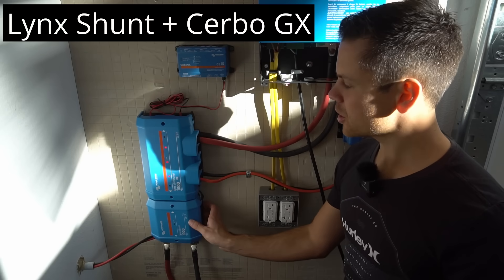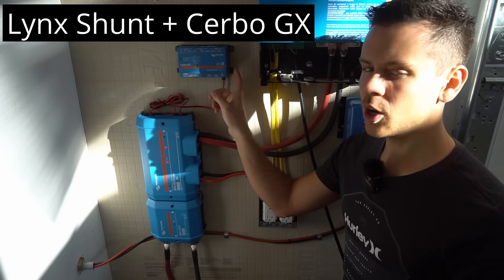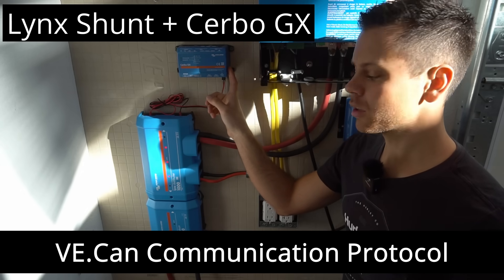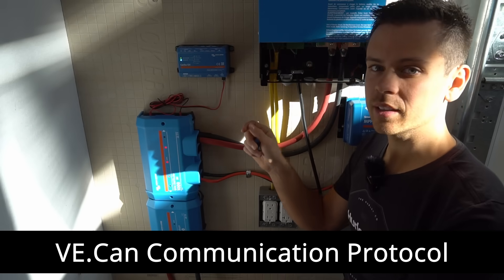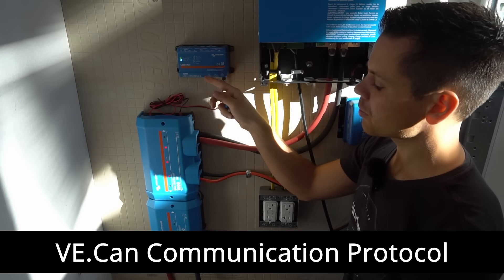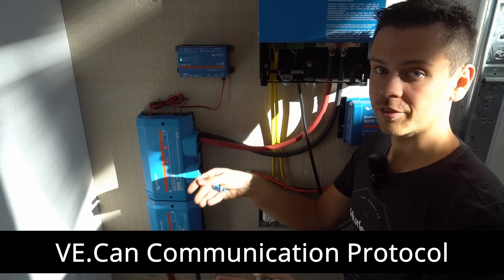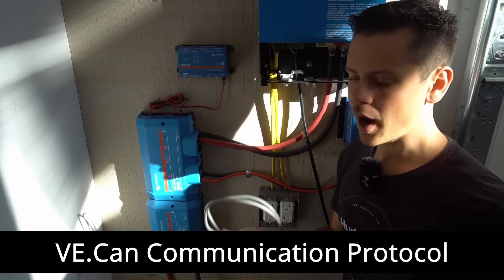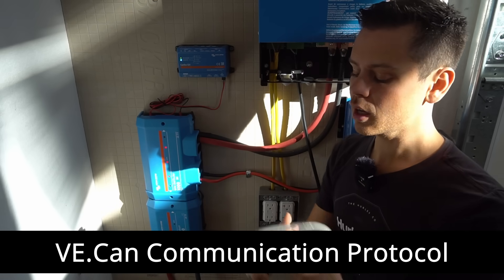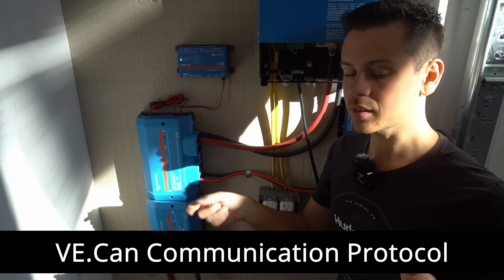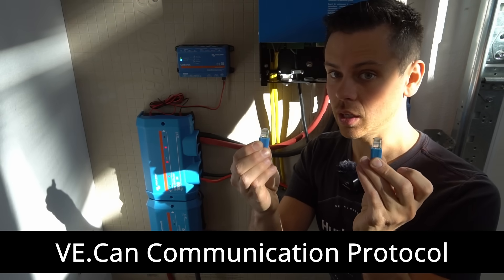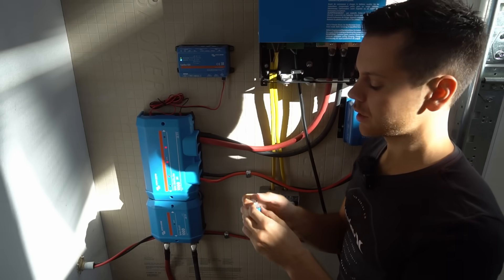Now first we're going to connect the shunt to the Cerbo GX with the VE or Victron Energy CAN communication protocol. And luckily we're only connecting two devices. You can use this VE CAN communication protocol to connect three or four or five different devices. But you need to know how to do it. Not only do you need cables to daisy link these together, but at the first and the last device you need to terminate it with these termination plugs.